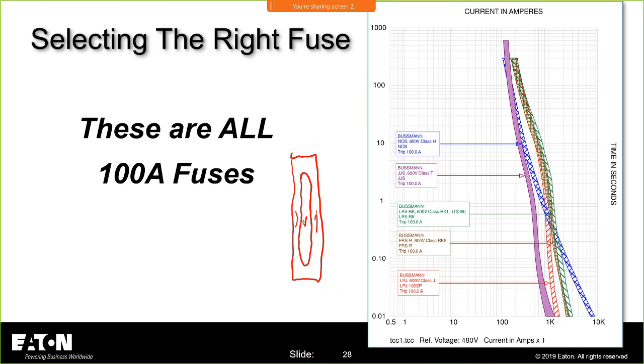You saw what the other fuses look like. Remember, you had that going on, and you had that going on. This is the Class H fuse on the right. These are your current limiting type fuses on the left, and this is what that fuse curve looks like. It's still a 100 amp fuse, but they have a low interrupting rating. They're not current limiting. But look at all of these other nice fuses.